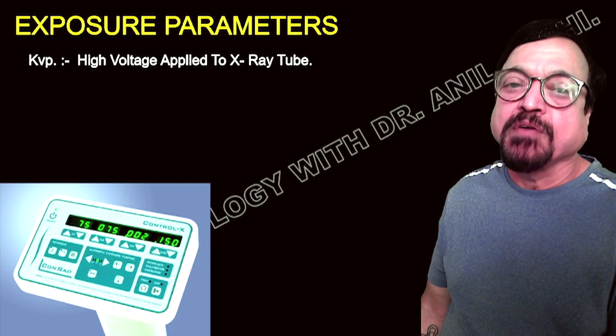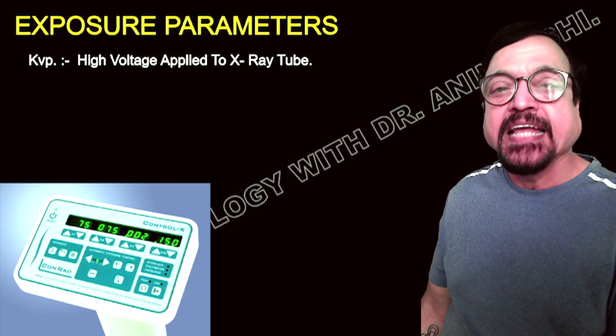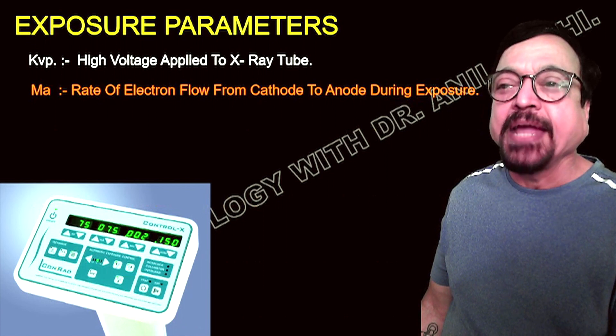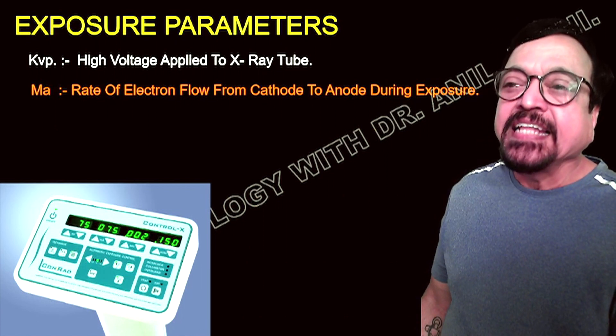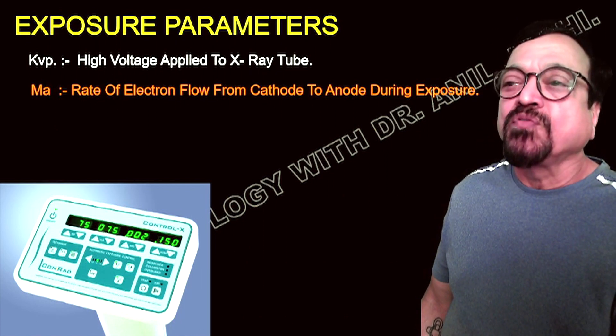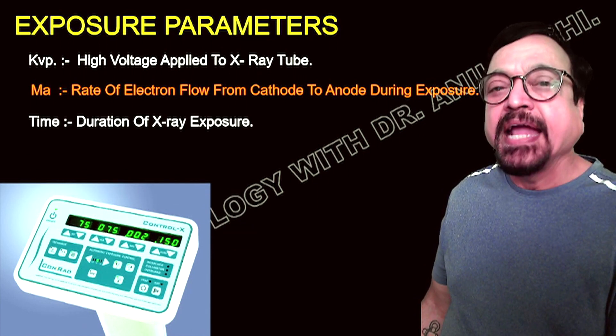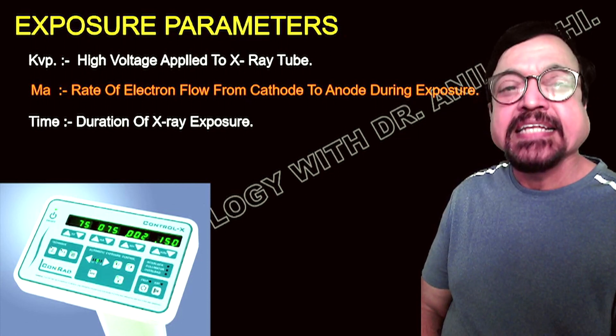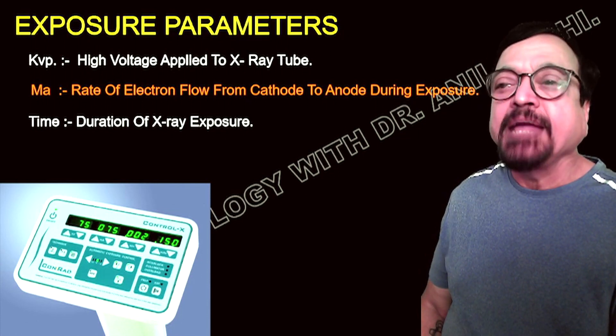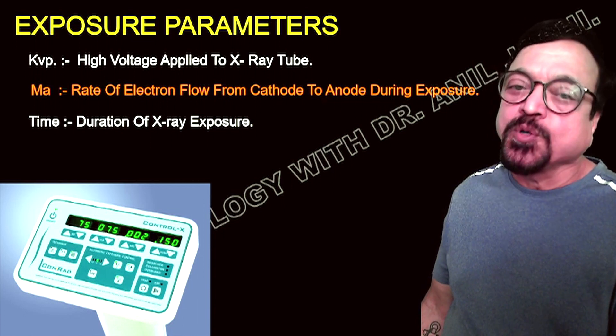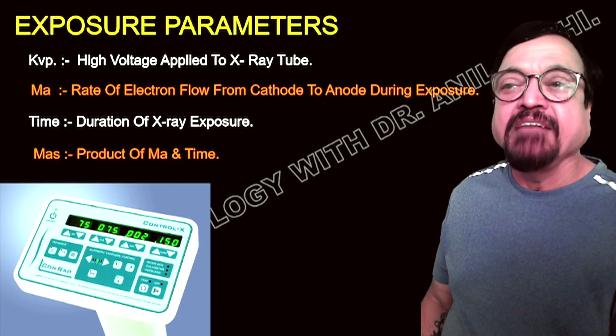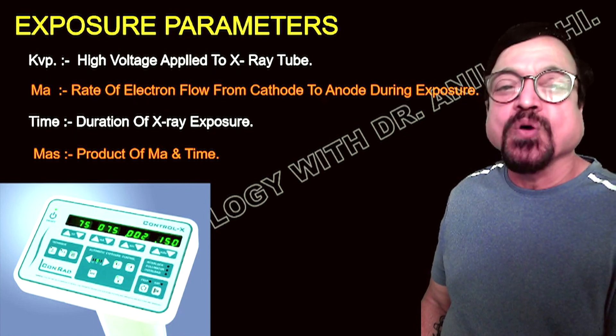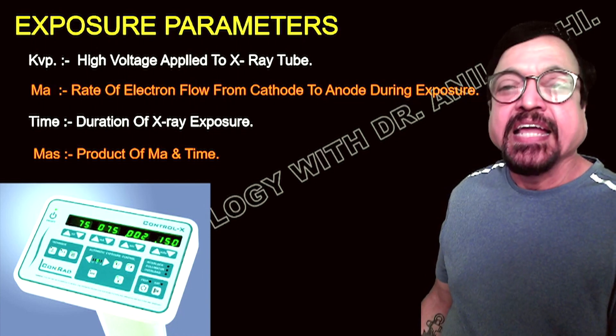The exposure parameters are: kV — the diagnostic range is 40 to 120 kV, with 60 to 80 kV being most commonly used; mA — the rate of electron flow from cathode to anode during exposure (increasing mA increases the number of x-rays/electrons); and time — the duration for which the exposure is on. These three — kV, mA, and time — are the basic exposure parameters.